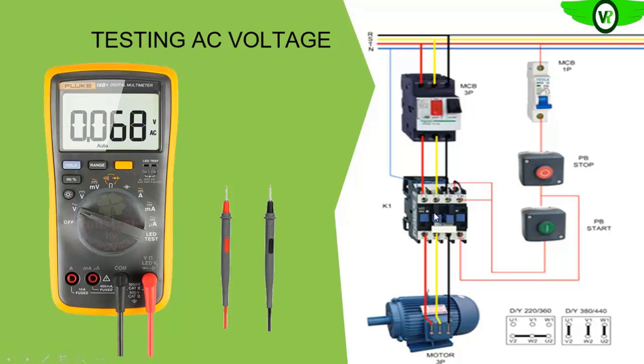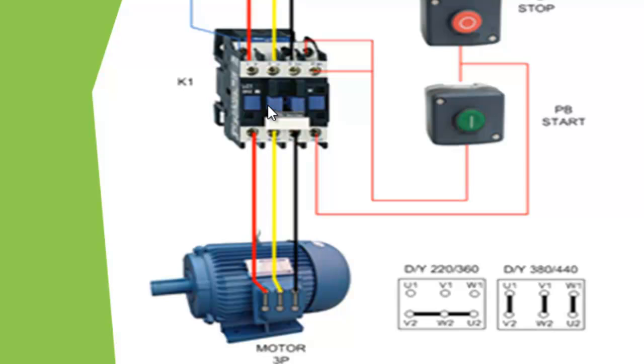So next, what you do is you can close it. If you want to work without the control circuit, you can manually close the contactor. But while you are closing the contactor, if it is safe to do so, you can close, because you know when you close, since the circuit breaker is closed, you are closing power to your electric motor. Your electric motor will start running. Okay, but if it is safe to do so, you can close. But if it is not safe to do so, you go to your motor end and disconnect the terminals, okay, and make it safe so that they don't breach. So whichever is convenient for your situation, that is what you will adopt.